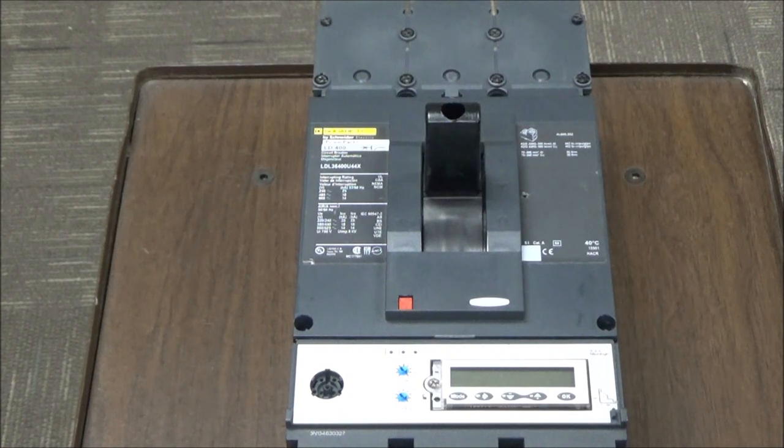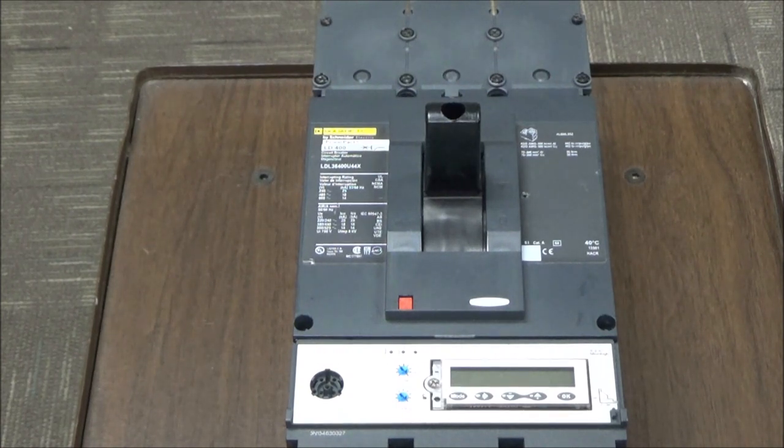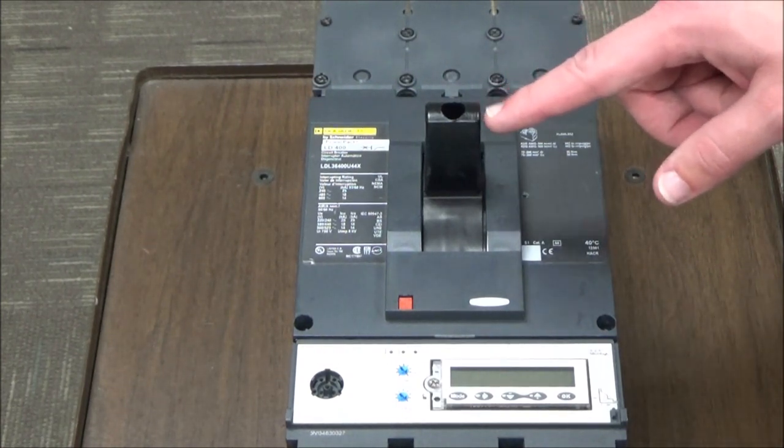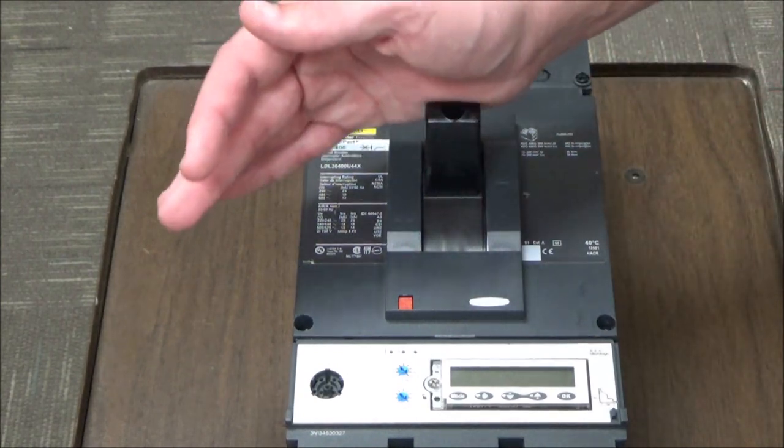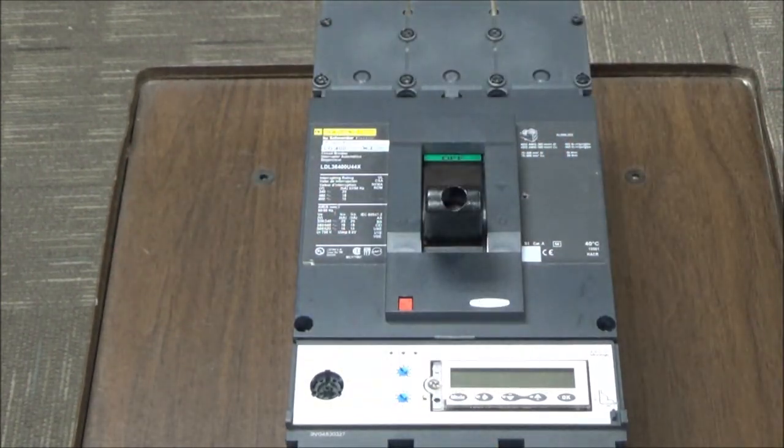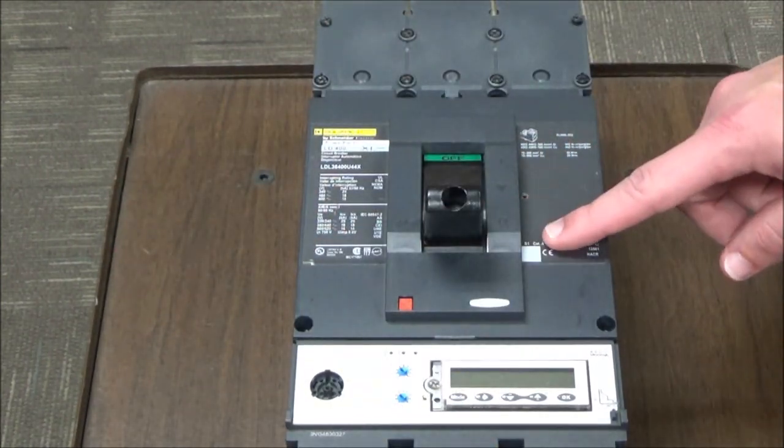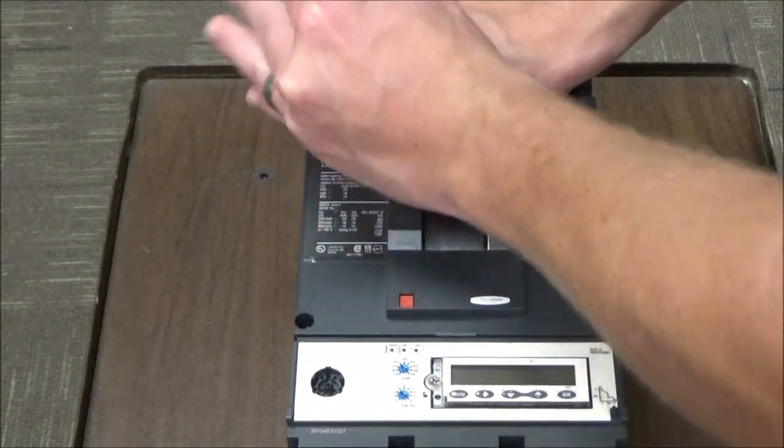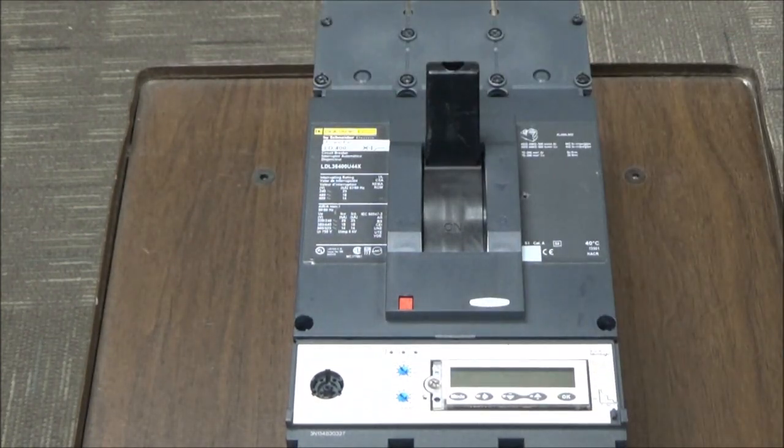To reset the PowerPact L-frame breaker you will take it from the trip position to the off position and then from the off position back to the on position like so.